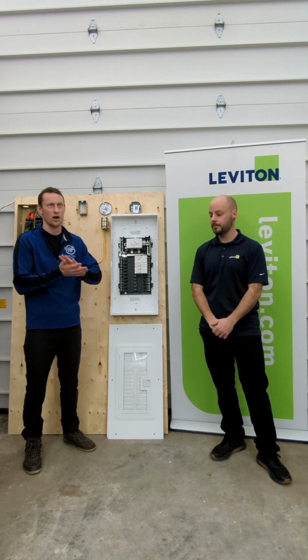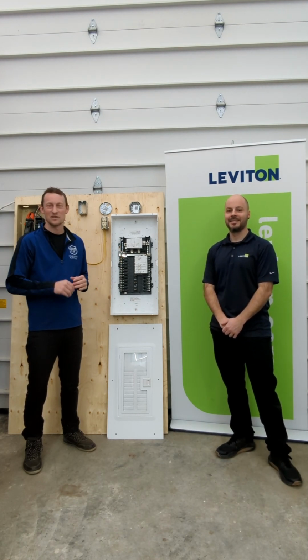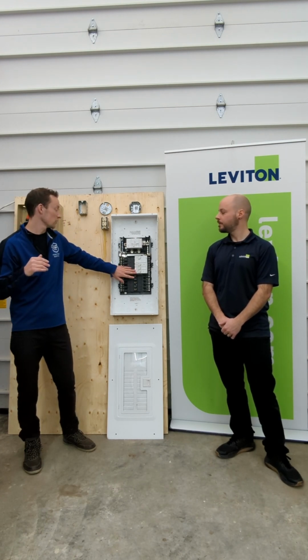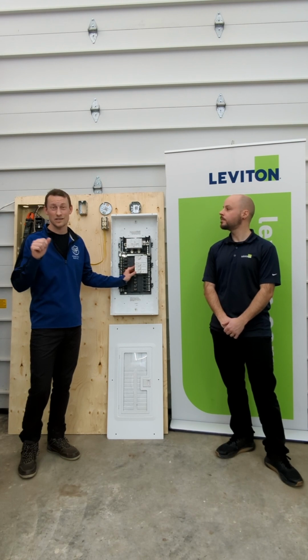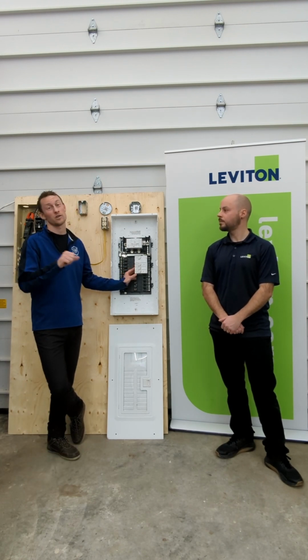There are a couple other options here for surge protectors too, because the whole point of these videos is we want to educate and entertain. More so educate, this isn't too entertaining. But surge protectors are typically going to have a value of maybe 60,000 amps that it can safely interrupt, or 100,000 amps. The same way other competitor breakers, I'm not sure with these ones, will typically safely interrupt and open the circuit at about 22,000 amps, when a typical circuit in your house is about 15 amps. So not anywhere close to that.